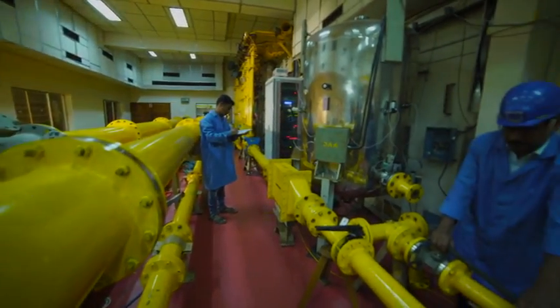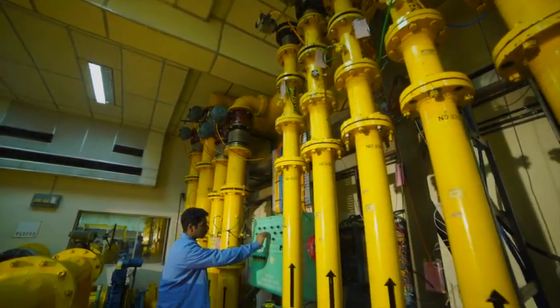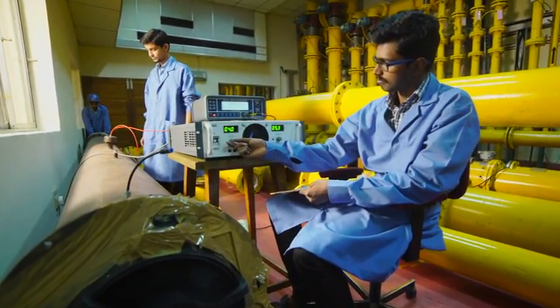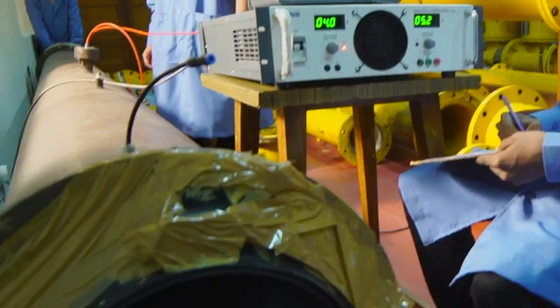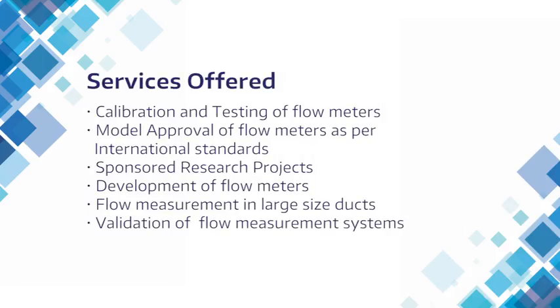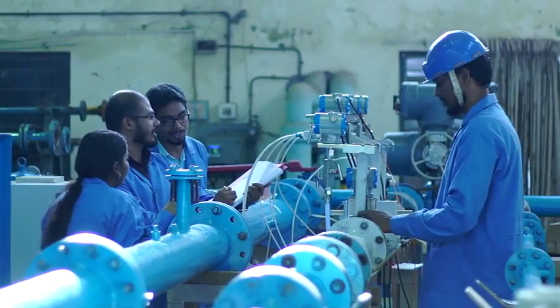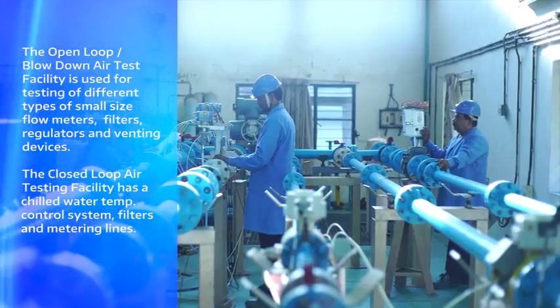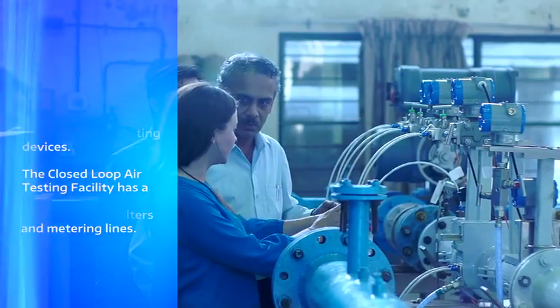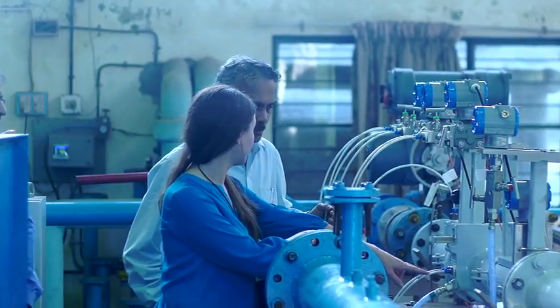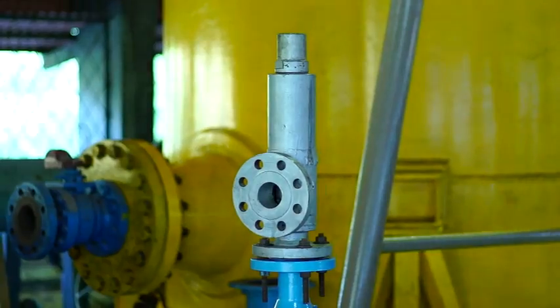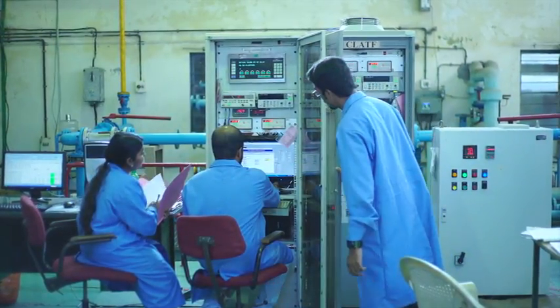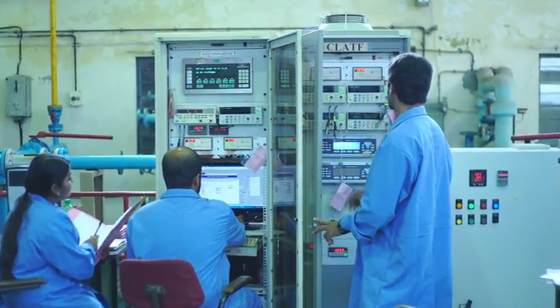Besides calibration, testing and model approval of flow meters, the services offered encompass sponsored research projects, development of flow meters, flow measurement in large-size ducts and validation of flow measurement systems. The 20-bar airflow lab needs special mention. The open-loop blow-down air test facility is used for testing of different types of small-size flow meters, filters, regulators, safety valves, air relief valves, breather valves and venting devices. The facility is also used for aerodynamic noise studies for valve trims and silencers.